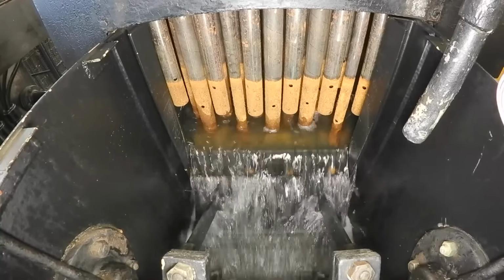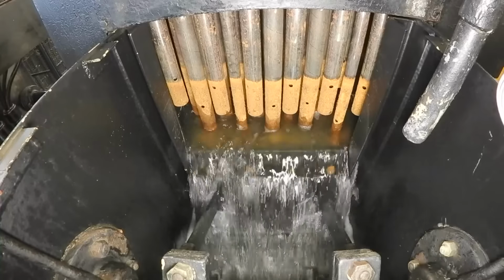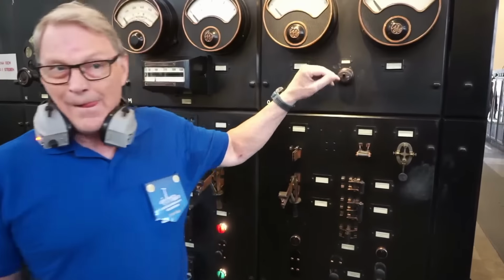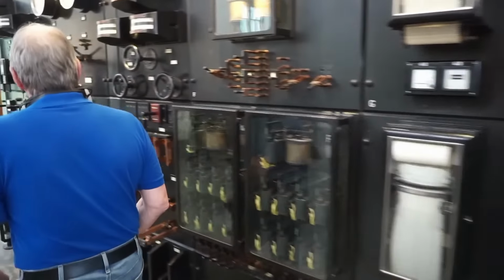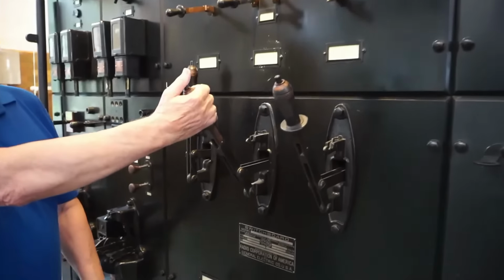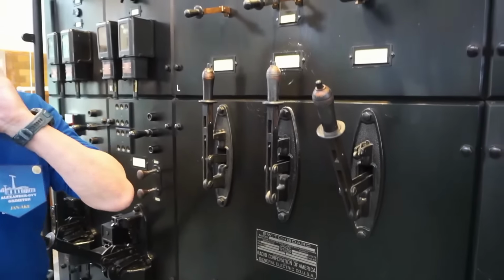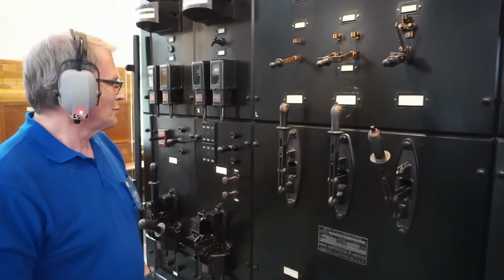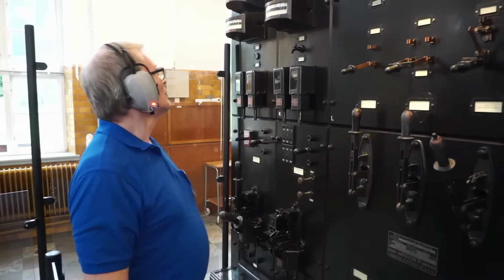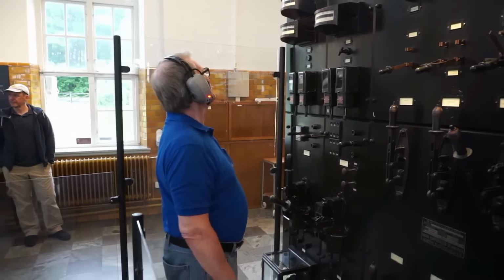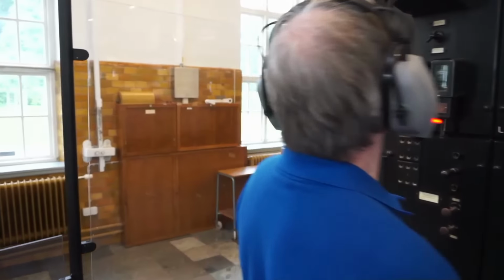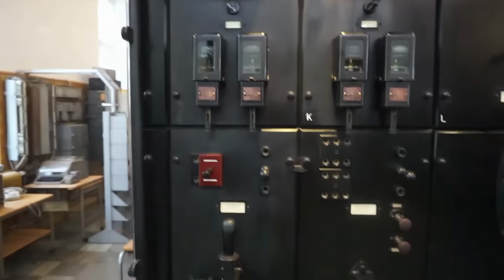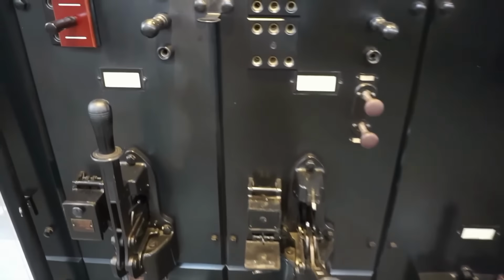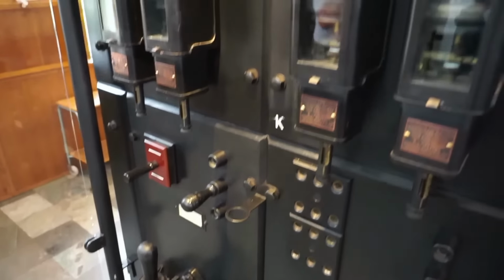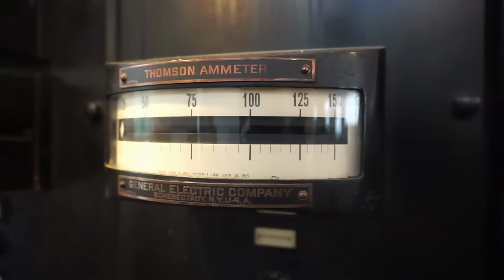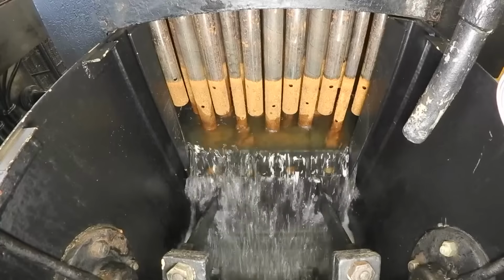Yep, we are ready, and we are going back to the control panel, and Jan-Åke will add the alarm bell again, and we have a persistent alarm because we have no lubrication. Jan-Åke will solve that, will start an auxiliary oil pump. Now we are ready to start up the main motor, and I will ask Jan-Åke to go to the emergency switch, because now we are handling 2.3 kilovolts two-phase. There are oil switches to extinguish electrical arcs.